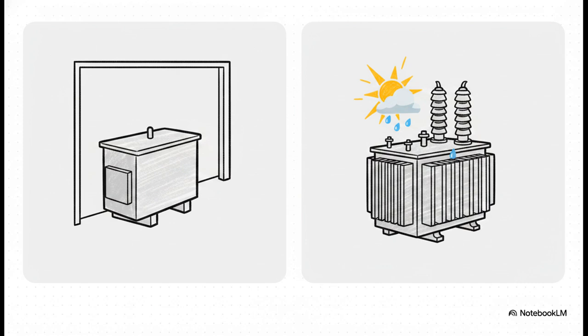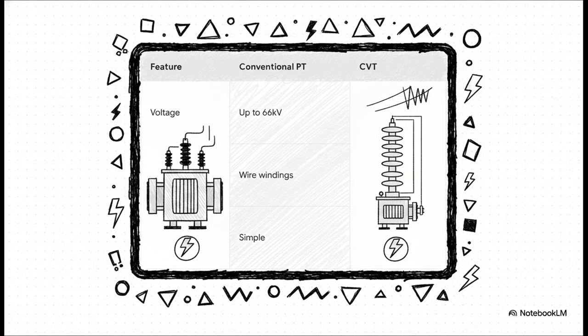But what about when we're dealing with truly monstrous voltages? Well, a conventional electromagnetic PT uses standard wire windings and a magnetic core, right? And they are simple and reliable for anything up to 33 kV, or maybe even 66 kV. But step into the big leagues, we're talking voltages above 132 kV, and a standard PT would require so much heavy, incredibly expensive insulation to keep from exploding that it would literally be the size of a 2-story house. Obviously, that is entirely impractical.